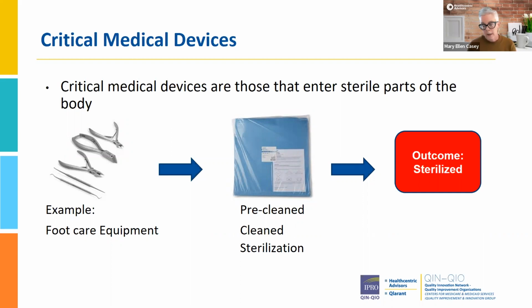So that may be using a solution that you spray on the instruments in a basin prior to them leaving the facility. And the goal of that is really to limit the bioburden from turning into cement. So there's bioburden on these instruments, and if it's left just to sit somewhere and dry, you literally have to chisel it off before you can even clean it. So certainly surveyors, if they're looking at reprocessing, they go right to the basin, they make sure all the instruments are open, and then everything is sprayed or moist before it's sent out, or it goes on to the next step of cleaning and sterilization. So something just to keep in mind, that it's a real process before it becomes sterilized.